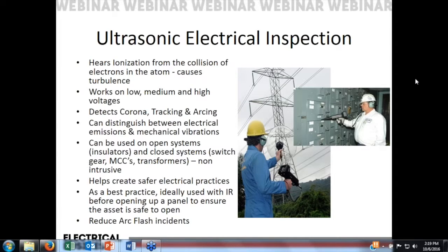Maybe we have an issue of a dry transformer where a winding is loose, or we have some delamination of the winding causing a vibration, versus actual electrical emission such as tracking, arcing, or corona. We can use our ultrasound technology and software to determine that. As I mentioned before, it can be used on open systems or enclosed systems. Open systems like insulators and substations, bushings, bus bars, etc., and closed systems like switchgear, MCCs, transformers, you name it.